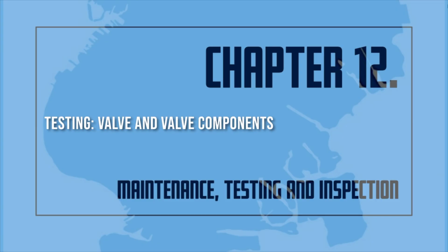C. Valve and valve components. Main drain test. This test shall be conducted annually at each water-based fire protection system riser to determine whether there has been a change in the condition of the water supply piping and control valves. Water flow alarms shall be tested quarterly in accordance with the manufacturer's instructions. Control valves. Each control valve shall be operated annually through its full range and returned to its normal position. This test shall be conducted every time the valve is closed.